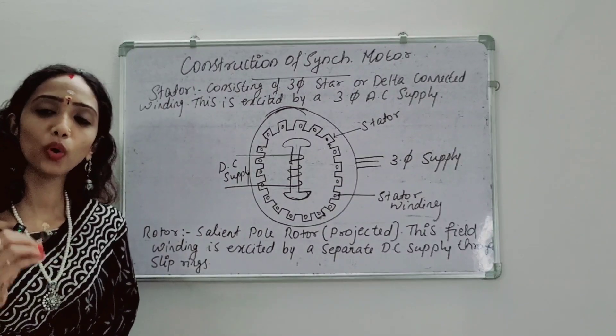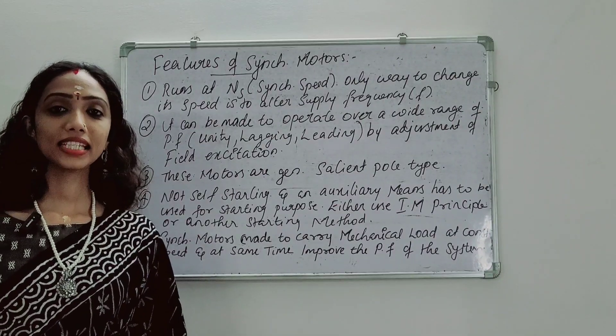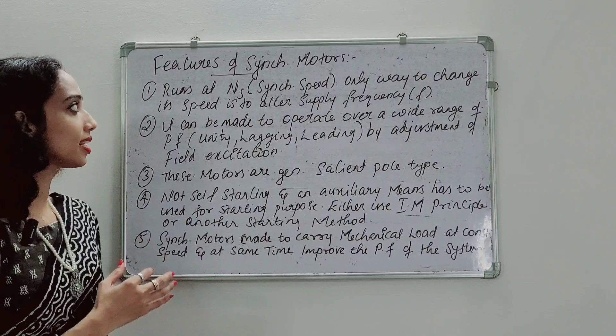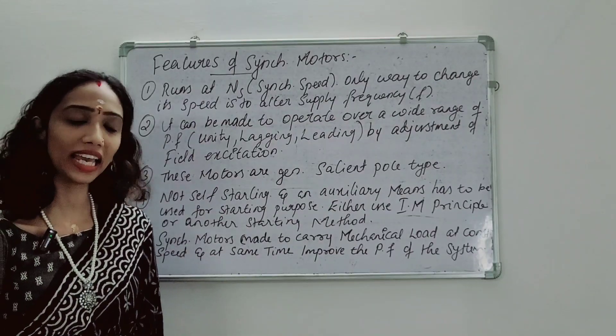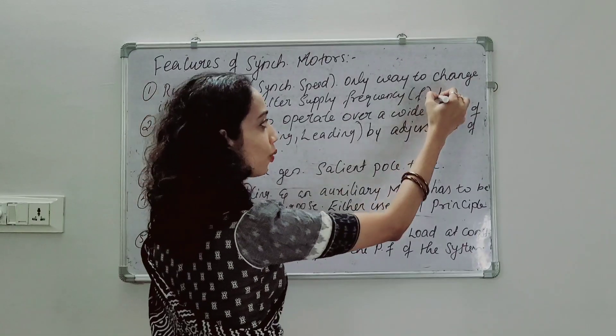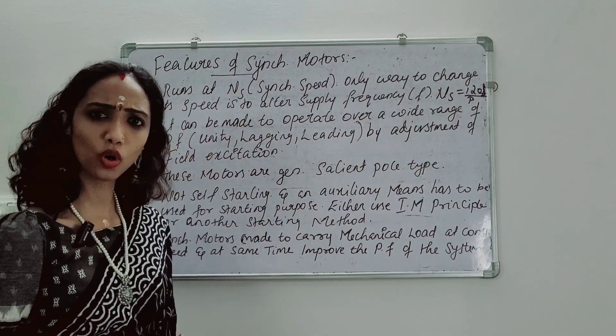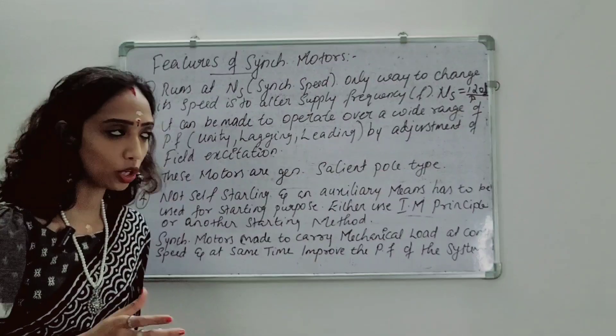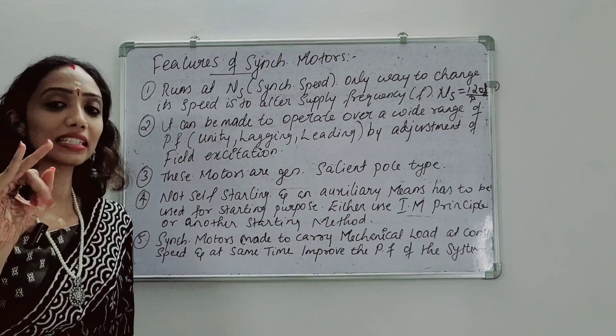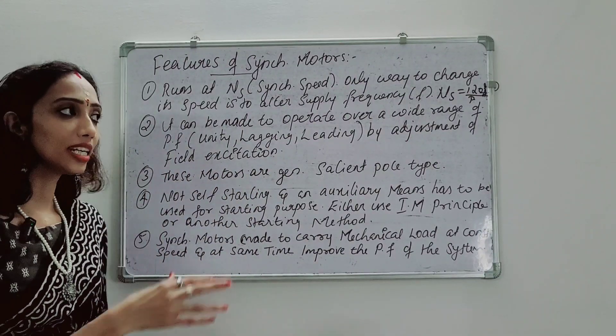Now, what are the features of Synchronous Motors? First, a Synchronous Motor runs at synchronous speed — it is not variable speed. The only way to change its speed is to alter the supply frequency f. Second, it can be made to operate over a wide range of power factor — unity power factor, lagging power factor, and leading power factor — by adjustment of field excitation.